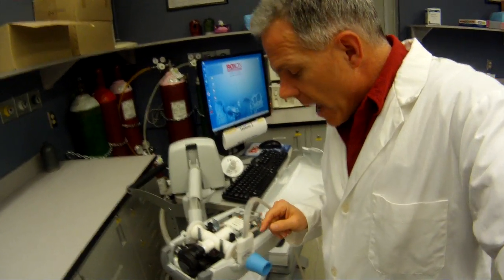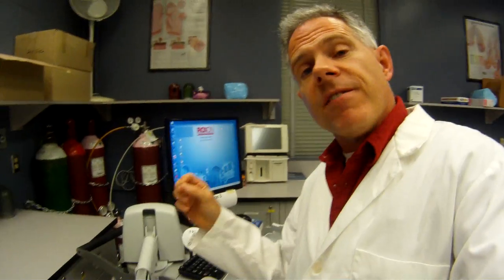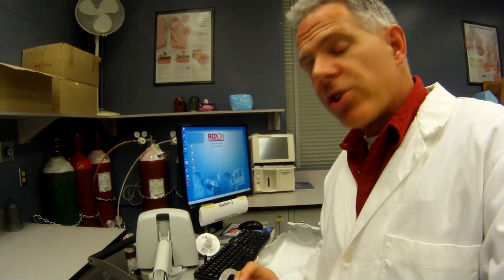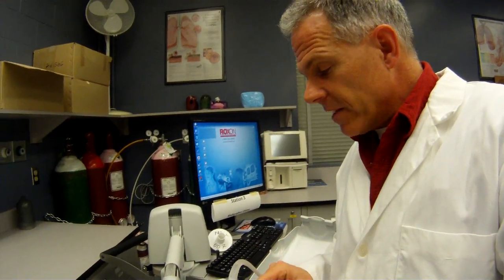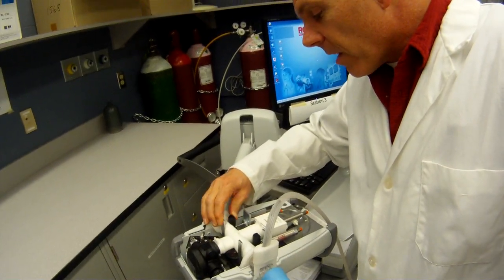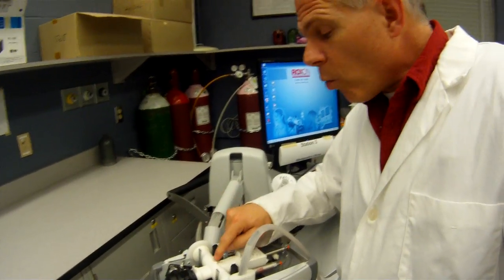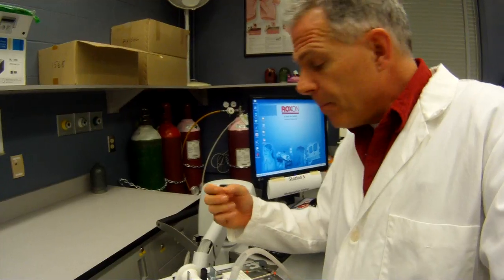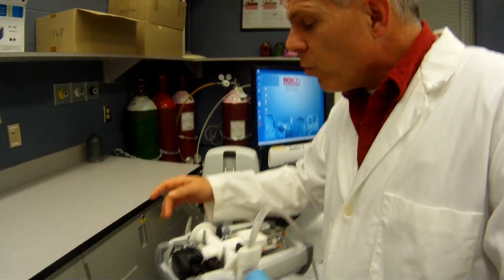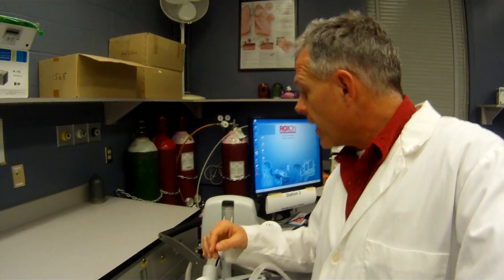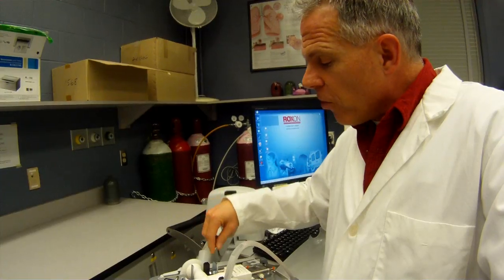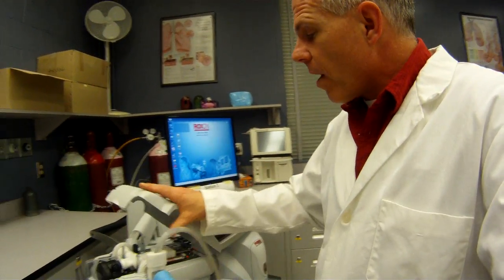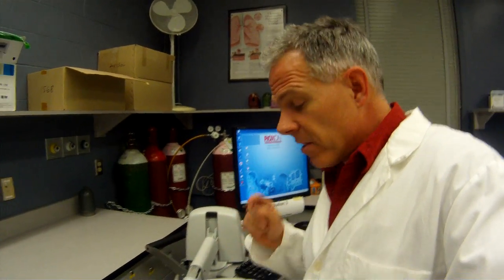Well, let's look at this little device here. What we have is our pneumotach. That's how this device measures the flow, the pressure gradients, and the volume. You can see it has some little valves inside, and this little rubber piece. It's important to watch for that, because if this gets ripped, which it will do over time, you need to be able to replace that. This black piece right here is the regulator. That's what the patient will be breathing through when we do specific tests like the nitrogen washout or the DLCO test. So it's important that all these valves be working properly, and that you're aware of how those hook up. The fact that those are gas operated means you need to have your gases hooked up for this device to work.